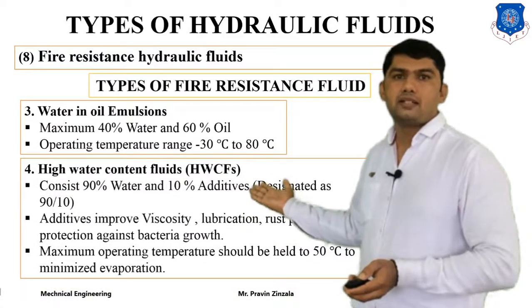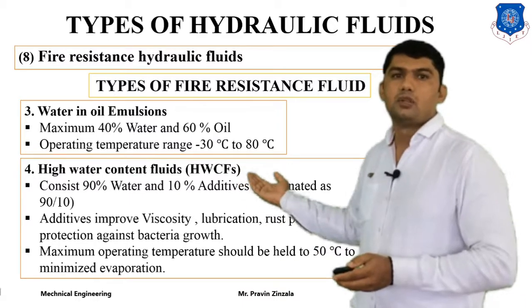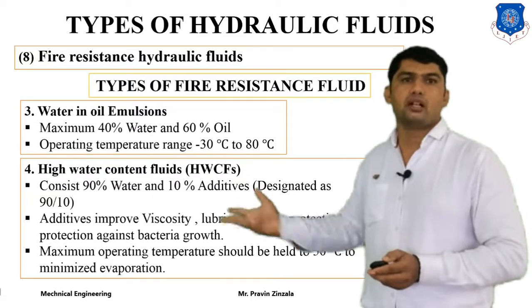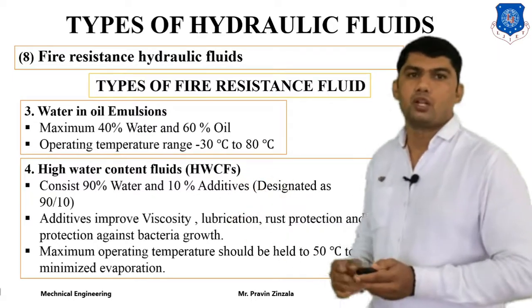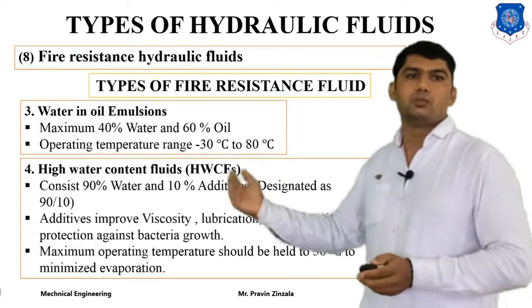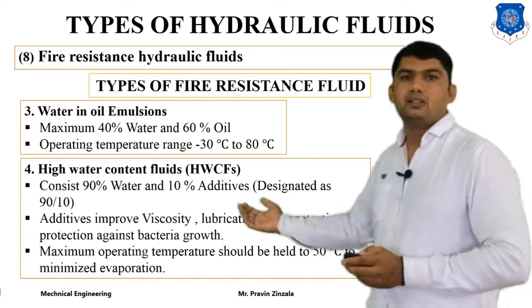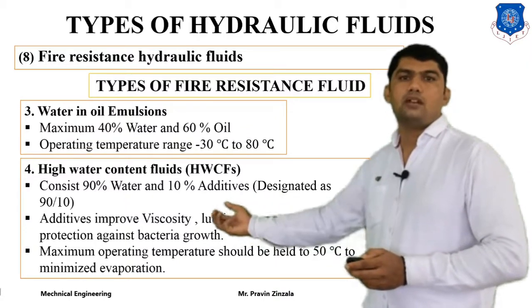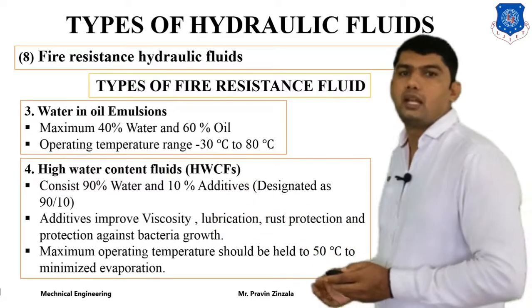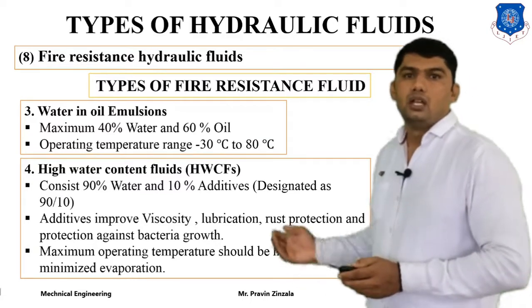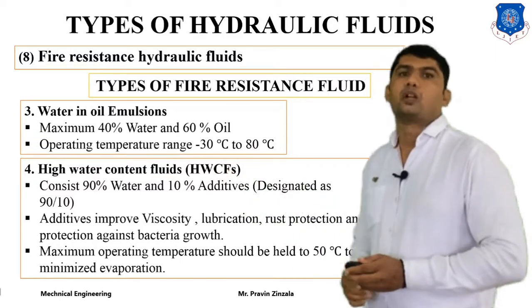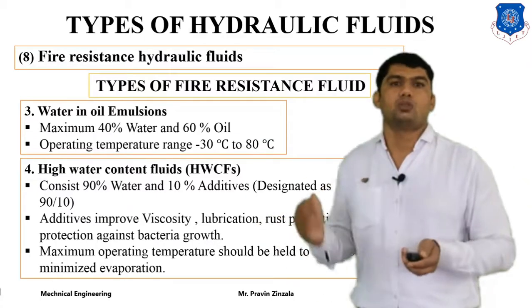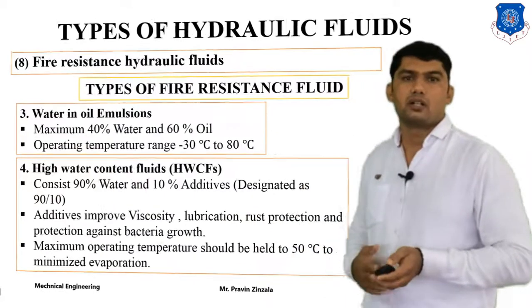The fourth fire resistance fluid is high water content fluid, called HWCF. It contains a maximum quantity of water and minimum quantity of additives. These additives improve the viscosity, lubrication, rust protection, and protection against bacteria growth. The maximum operating temperature is 50 degrees centigrade. Above 50 degrees, water starts to evaporate, which is a disadvantage of high water content fluid.